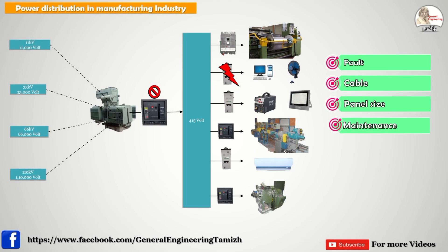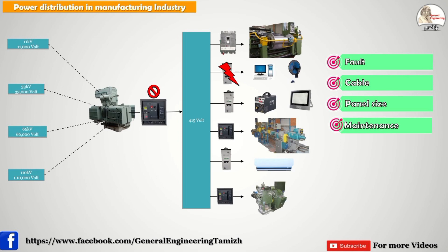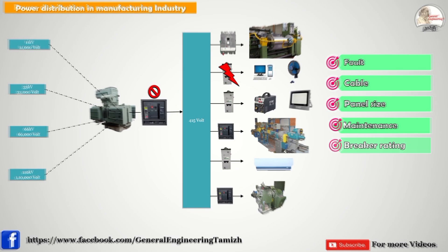The next scenario is maintenance. For example, if I need to service one breaker, I have to switch off the incomer breaker. If the incomer breaker is off, the total plant supply is disconnected. I cannot stop the total plant just to service one breaker. So from a maintenance perspective, this system is also not suitable.